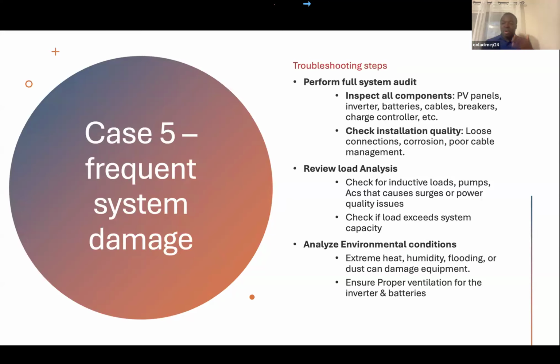And a peculiar situation like this requires more work because this is not regular. You've installed one, maybe it might be an inverter, it might be a battery, and what you realize is that it goes bad, you replace it, it goes bad again. Then you have to do more than what you have been doing in terms of troubleshooting. The first thing you want to do is perform a full energy audit, inspect all components: the PV, the inverters, the battery cables, breakers, charge controllers. You have to do a thorough investigation.